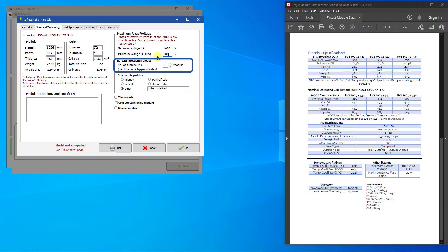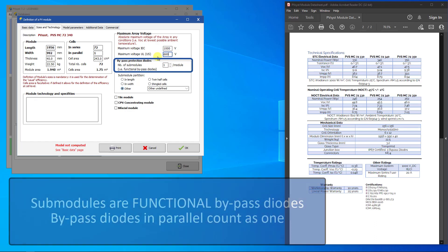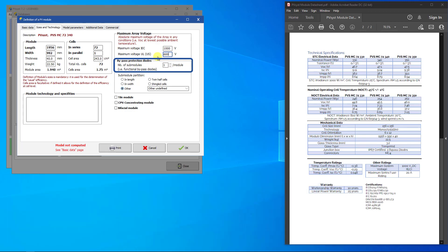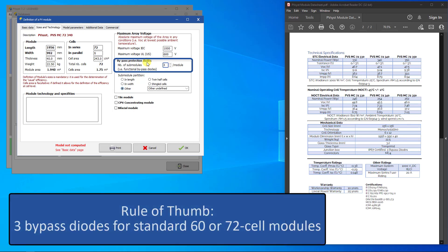In this field, you enter the number of submodules, which is equal to the number of protection bypass diodes. This concerns functional bypass diodes, which define the partitioning of the module into submodules. Sometimes, manufacturers connect two diodes in parallel, which makes 6 diodes for a standard PV module. However, in the pan file, this has to be counted for as 3 functional bypass diodes. Manufacturers do not always provide the number of bypass diodes on the datasheet. If you do not know the number of bypass diodes, you can use a default value of 3 bypass diodes for standard 72 or 60 cell modules.